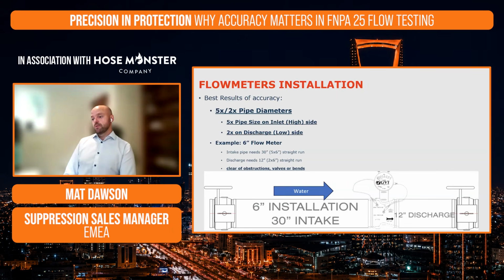So just a note, when we're installing, just a few installation considerations to take into account. We do need to make sure that we've got 5 times pipe length compared to diameter on the intake. So in the instance on the image, we've got a 6-inch pipe. So it's a 6-inch installation. That would mean we would need 30 inches of pipe beforehand.